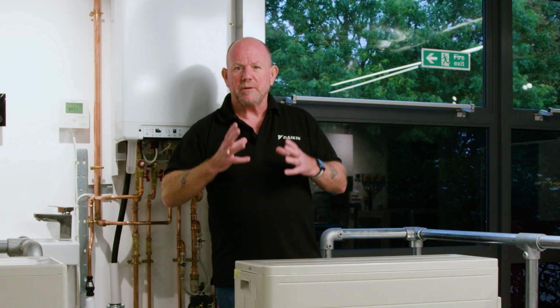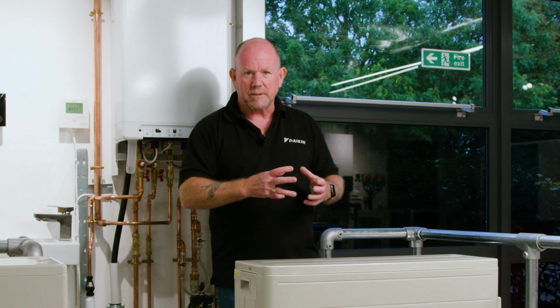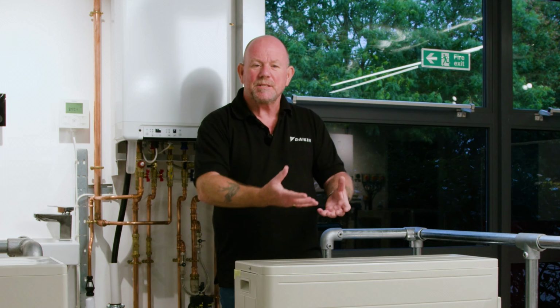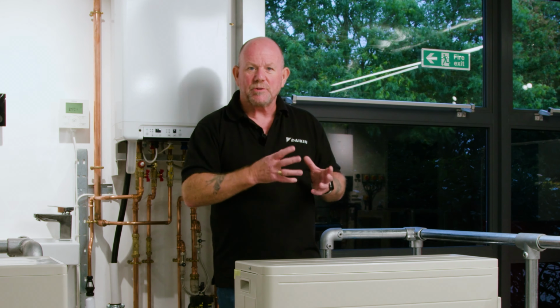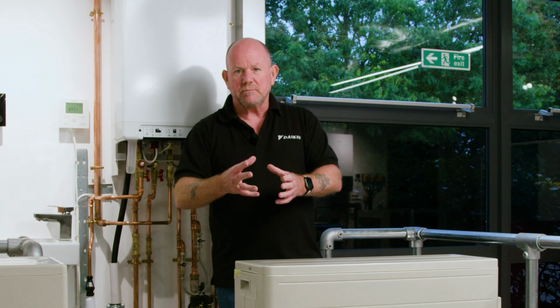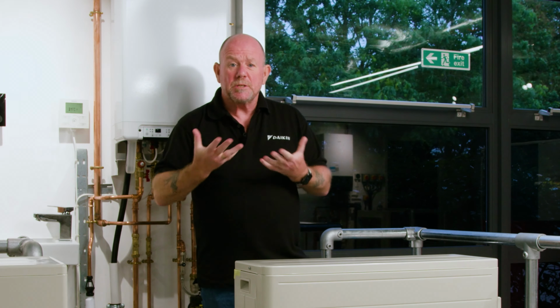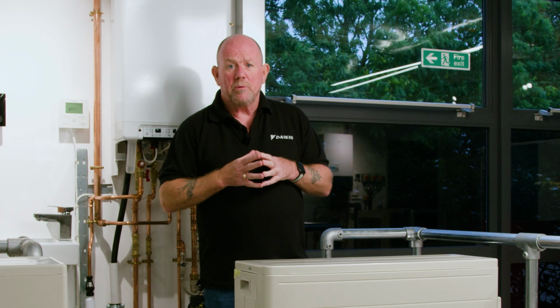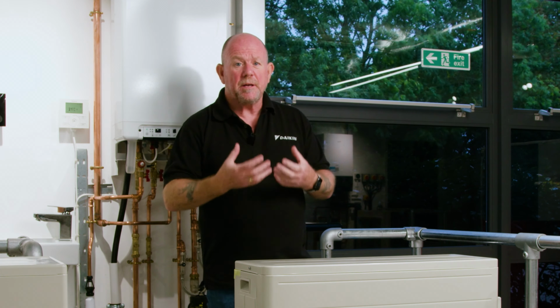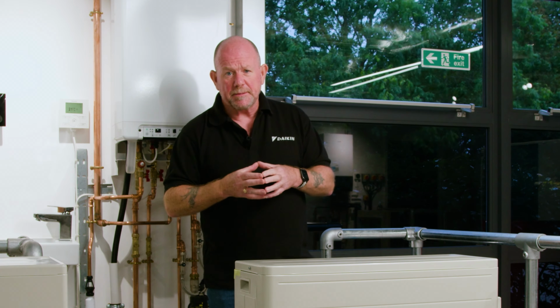And of course, we mustn't forget the requirement for a system filter. Our outdoor unit does contain a strainer. That strainer is last gasp protection. The system should have its own filter. And again, the British standard and Part L tells us that. So once you've dealt with your system water quality, we're almost at the stage where we can start thinking about setting the system to work.